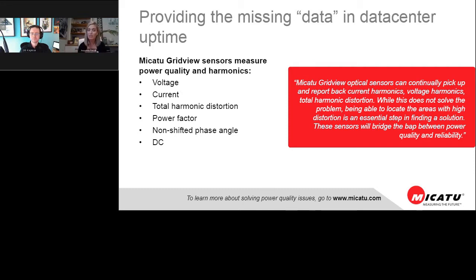From the data center perspective, there's two ways to look at it. One is, let's verify when you're consuming power from the utility, that you're getting what you need, let's verify the power coming in is clean, meaning good power quality. That's how I had always thought of it, which, they've got standards, and most of the time you're going to get great power from your utility, unless something is very wrong.